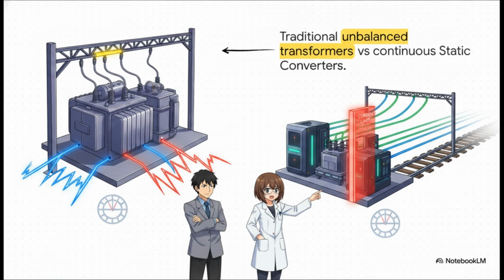But the modern fix? Those are static frequency converters, or SFCs. They use advanced power electronics to balance the grid perfectly. But there's a catch. They have a fatal flaw: hard, absolute current limits. If a train asks for way too much power all at once, the SFC can't just push through it. It actively cuts the power off to protect itself.